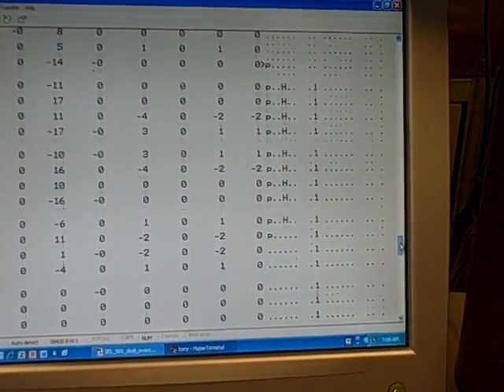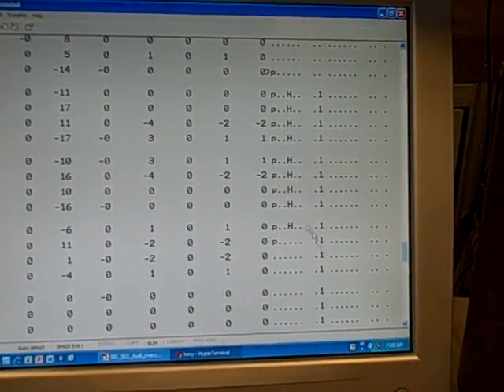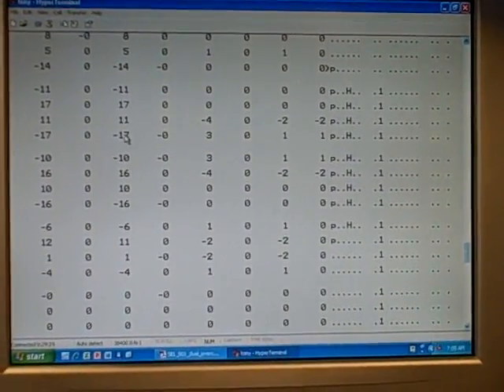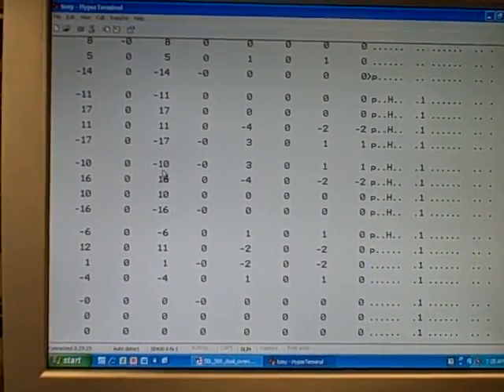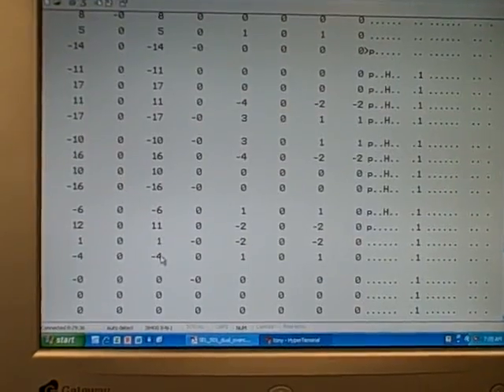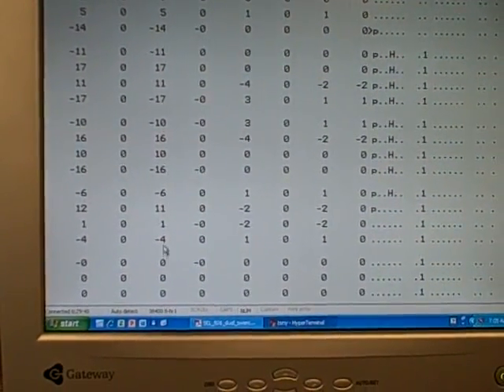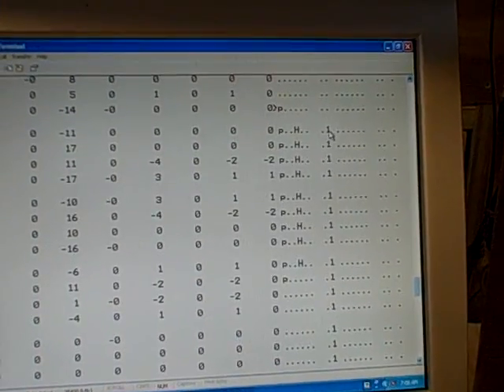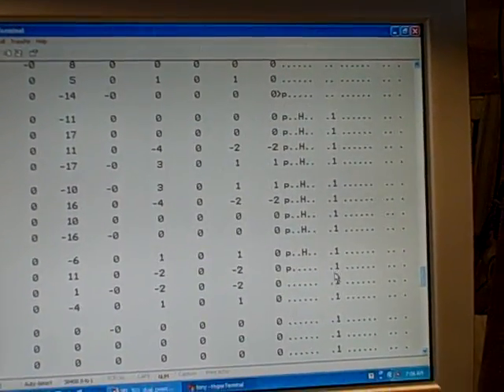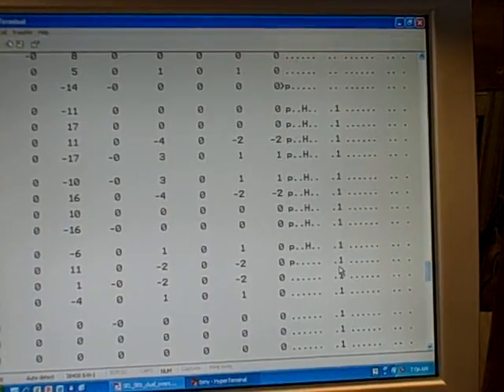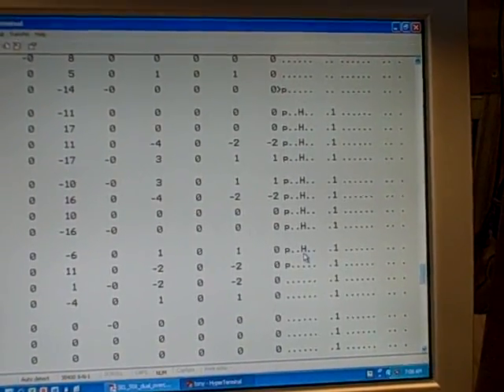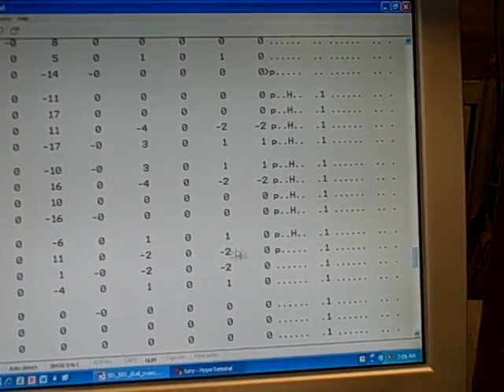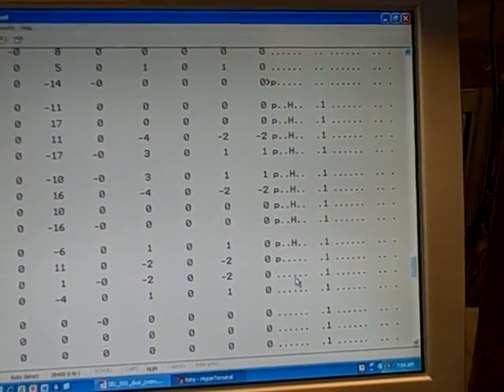Now this gets really interesting here. Notice how we have an output here of 1 all the way down. Notice what happens to our actual current values. We still have a full cycle of AC current peaking at about 17 amps. Then here we have a full cycle of AC current peaking at 16 amps. Then right here, halfway through this cycle, the current seems to fall off dramatically. And by this cycle right here, we have no more current anymore. In other words, what has happened is the circuit breaker has opened. We have initiated a trip event right here, the relay has asserted its output contact, but it's taken this long for the circuit breaker to actually open. We're looking at a delay in the circuit breaker of about two and a half cycles worth of time. Notice here, the 50P element is no longer showing an H, no longer showing an instantaneous. Because when the circuit breaker tripped, the current has fallen below the pickup value, and it no longer is picking up that element.